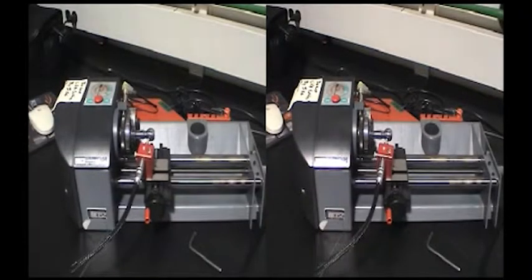This is the cracked part in a lathe with a probe attached next to the spinning ball end of the part that has the crack. Each time the crack goes past the probe, there will be a jump in the eddy current response of the instrument.